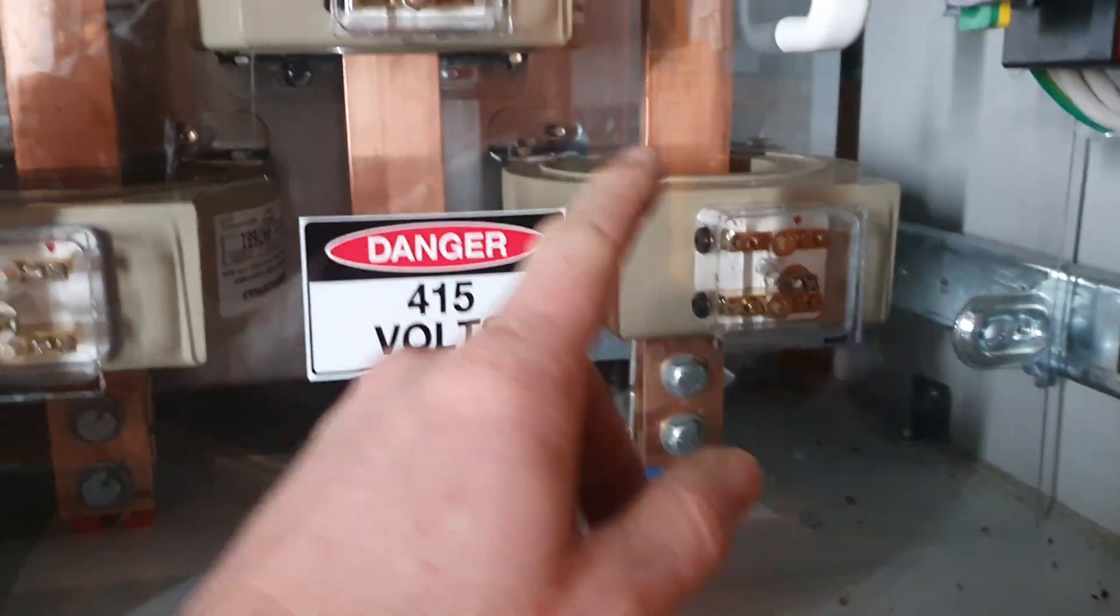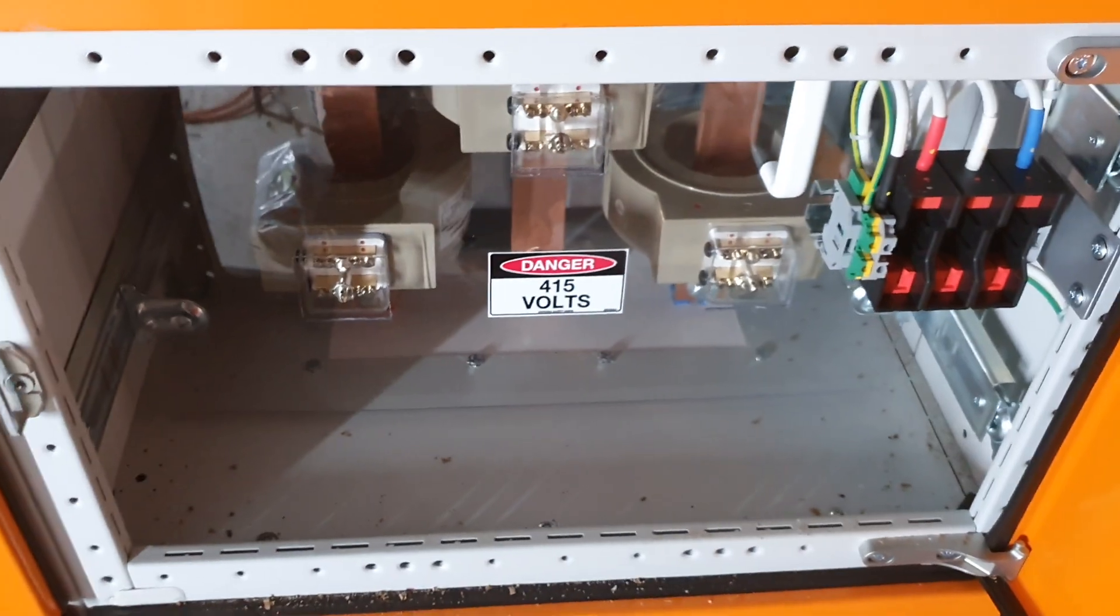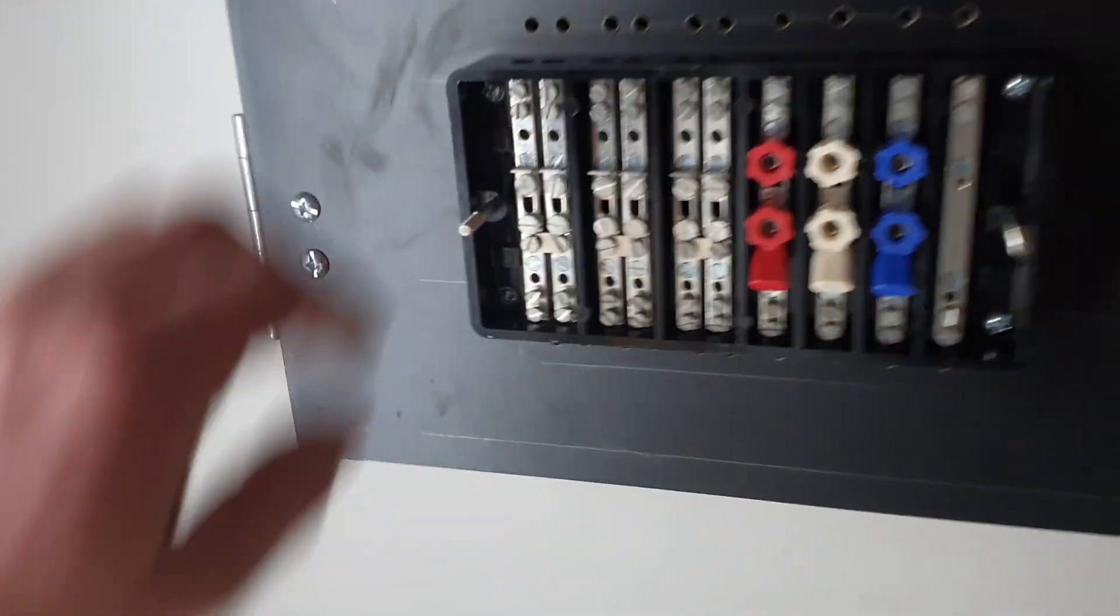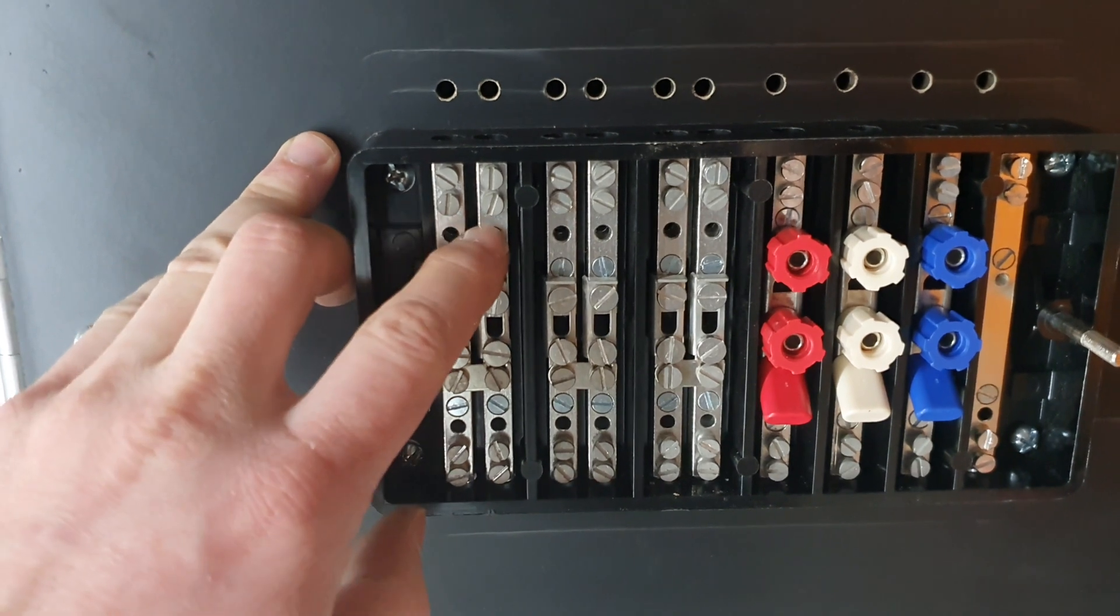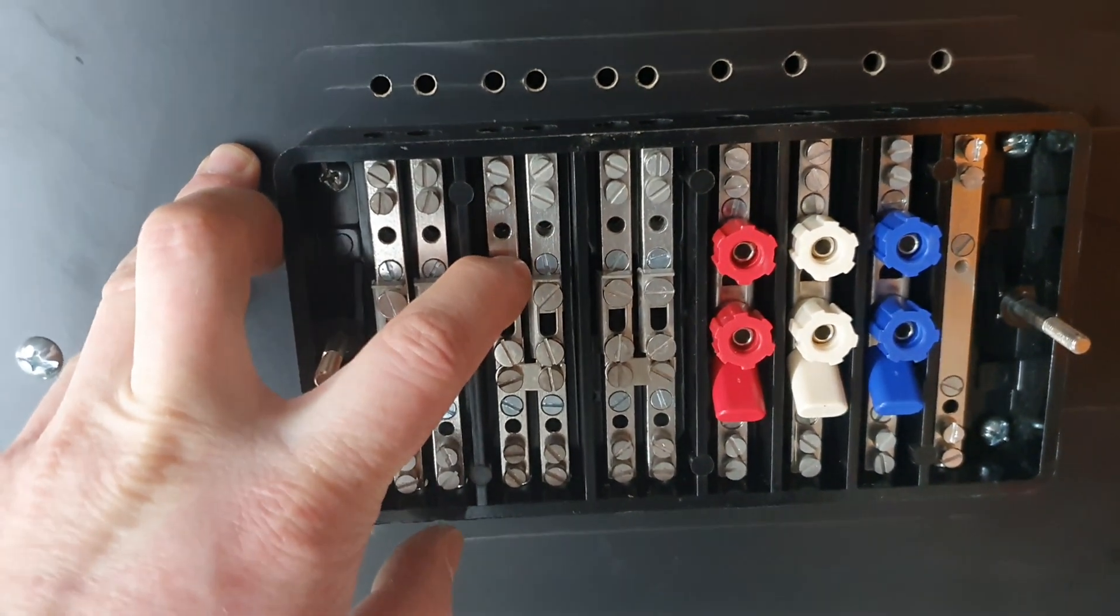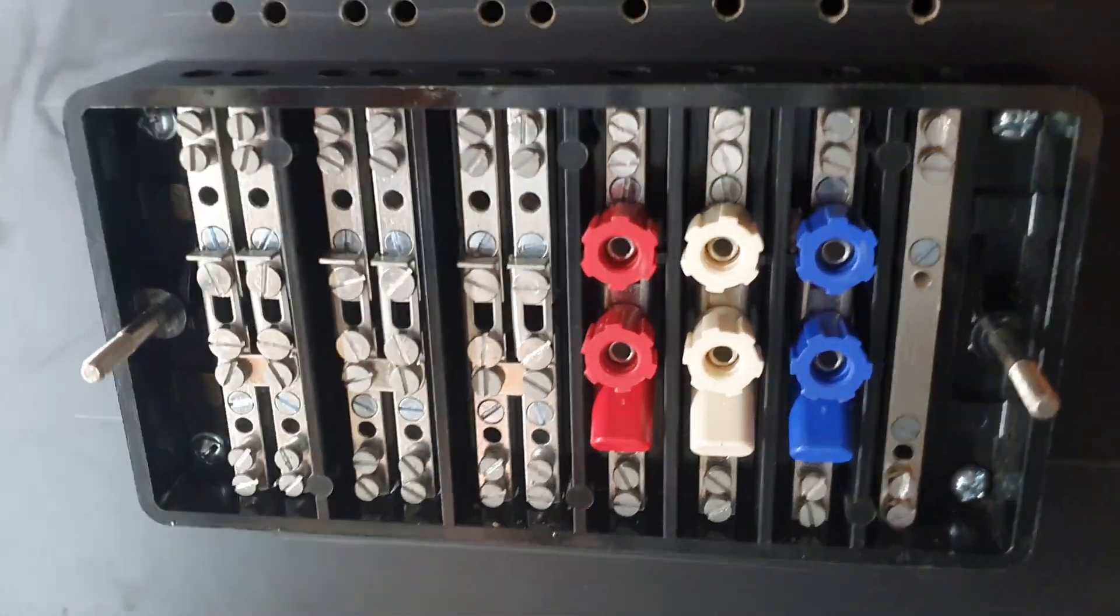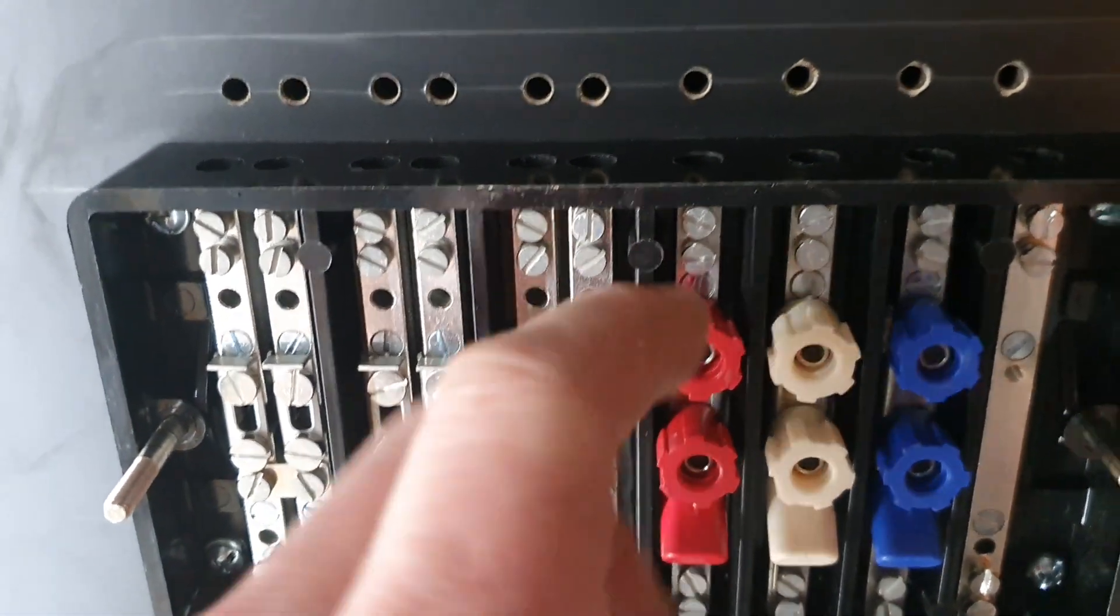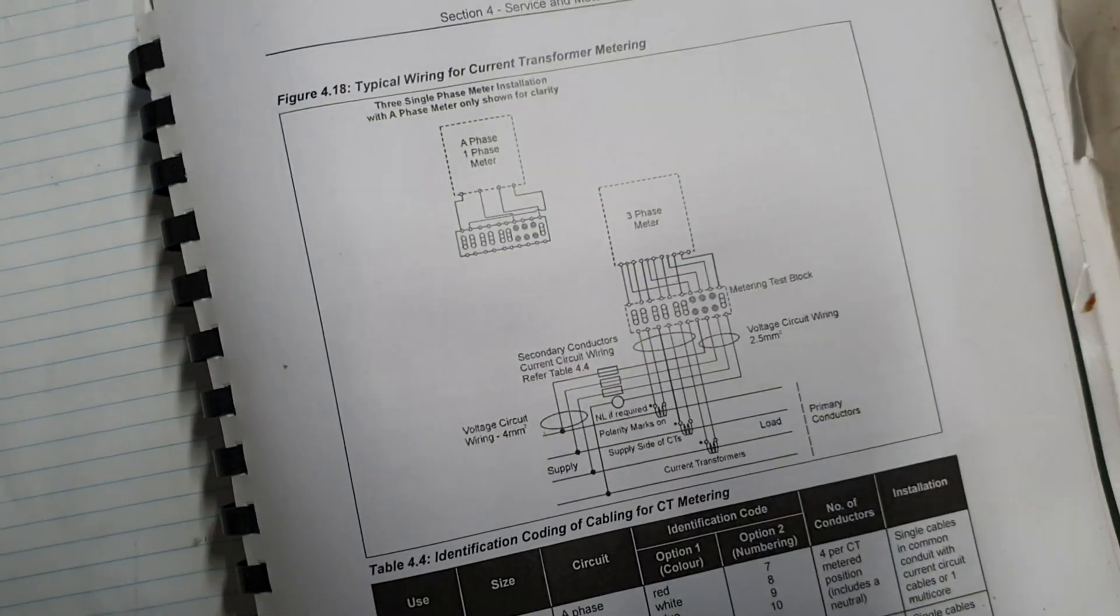So that cable will run up over here and down here to this test block. So on this test block you've got the coils, so this is an electromagnet or electromagnetic sensor coil two or three. And then you've got your voltage and your neutral voltage reference. It's a voltage reference because you need the voltage and the current to work out the power and that's what the meter is reading. It's reading your kilowatt hours.